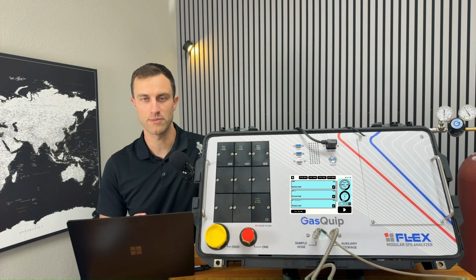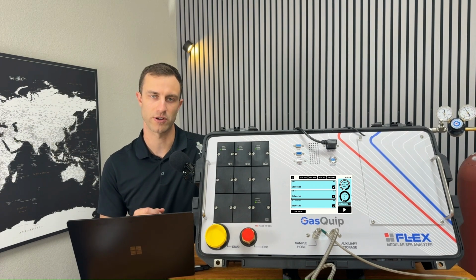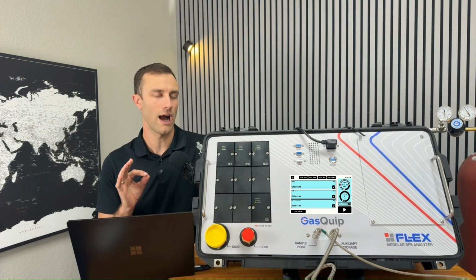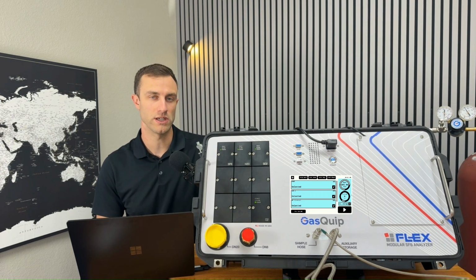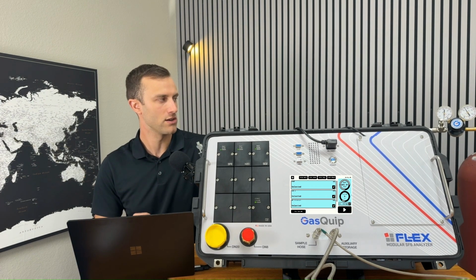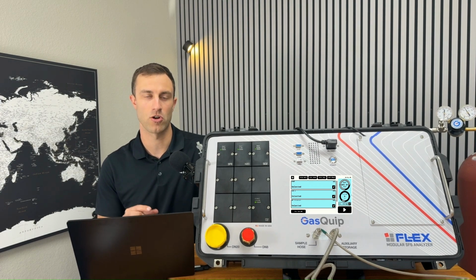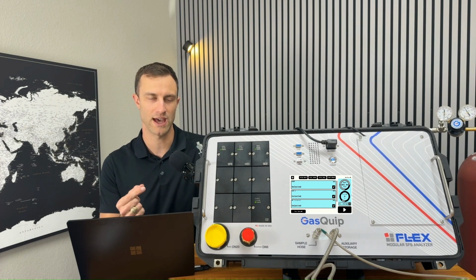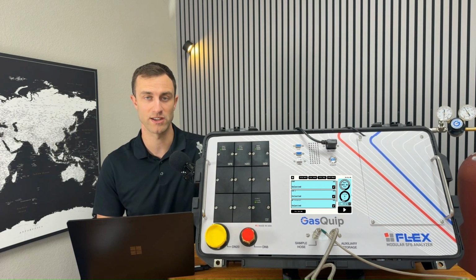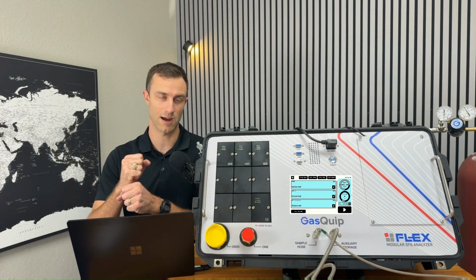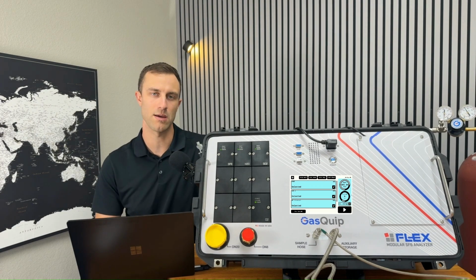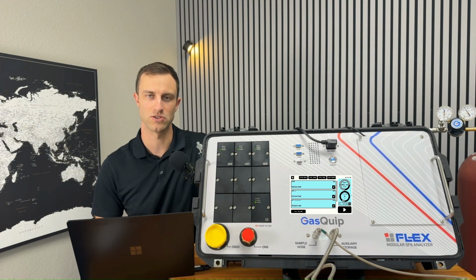So let's talk about a few general tips when it comes to testing that should help you get a better experience out of your analyzer, any analyzer for that matter. I would recommend always having a dry regulator that you keep in a dry box or area that you can always hook up for testing on a bottle. Also, try to always use the shortest amount of fittings together that you can. I've seen a lot of times where guys are using these Frankenstein type fittings, with one adapter on top of another adapter on top of another adapter, with sealants and PTFE tape, and it's just a long pipe-looking Frankenstein adapter that is not good for testing, because it introduces more and more areas for leaks and points of entry for ambient air to get into your sample.